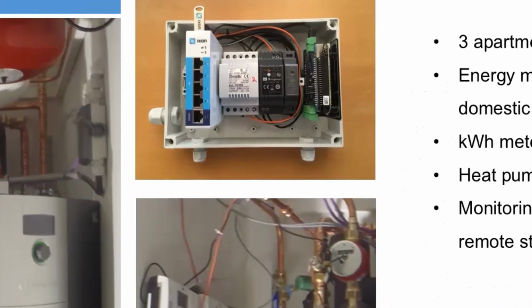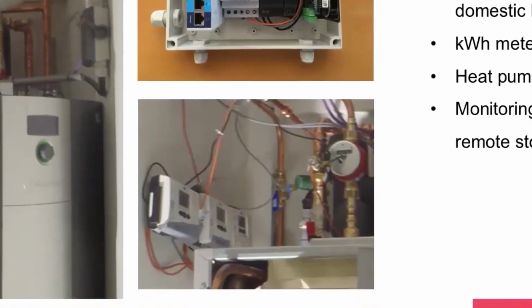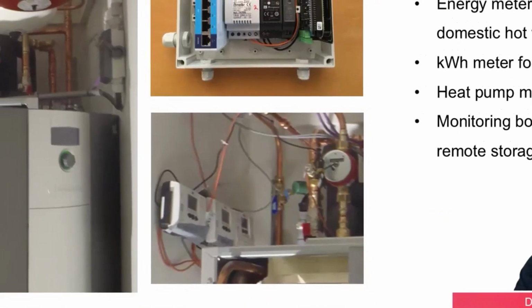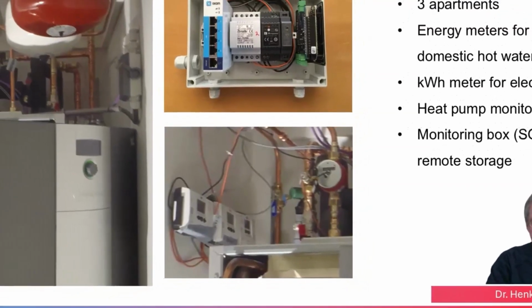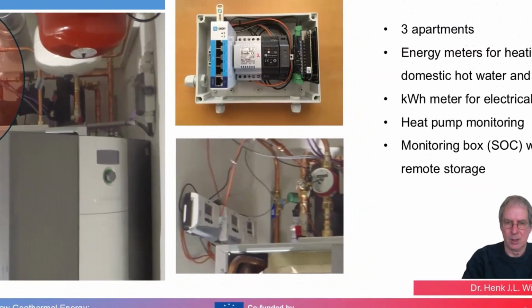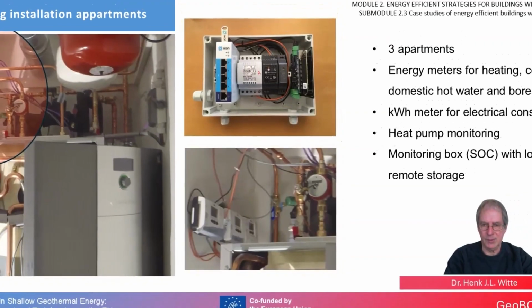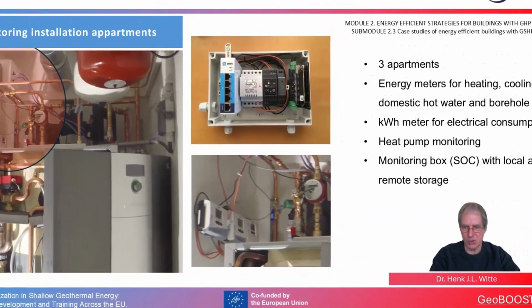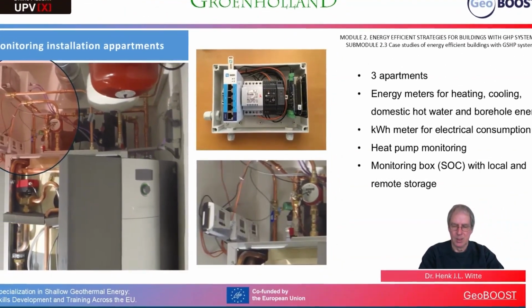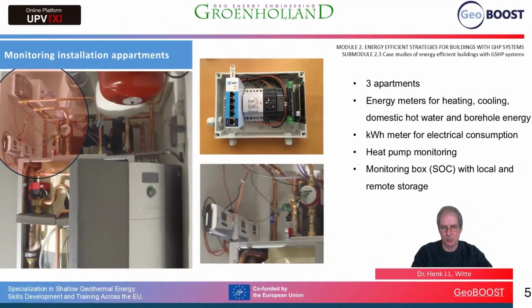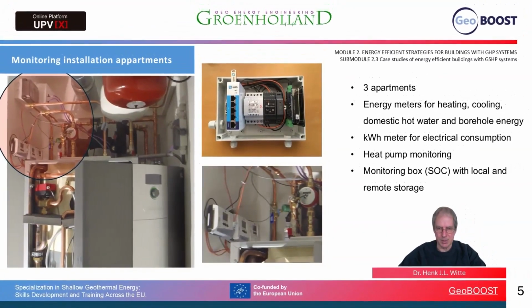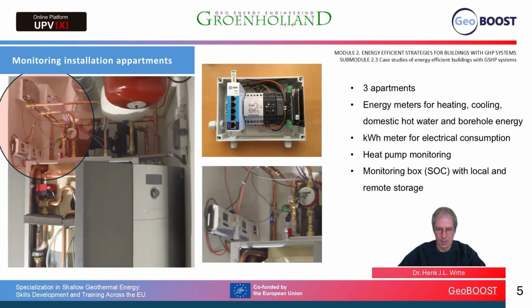On the top, you can see a little box with 2 cables going in. On the right, you can see this box opened up, and here you can see an Ixon VPN router that we used for the external connection, and a little data logger that Groen Holland developed based on a system on a chip, an actual BeagleBone little low-cost computer with a Modbus interface to read out all the energy meters and also read out the heat pump data.